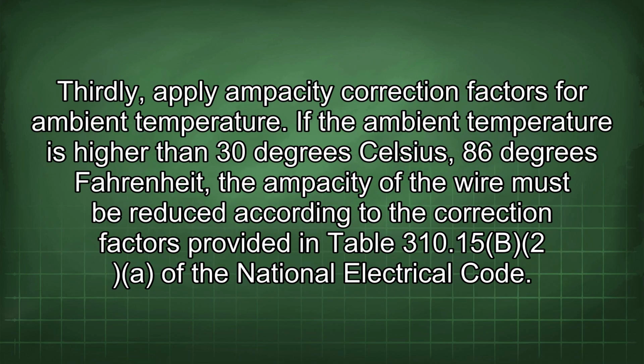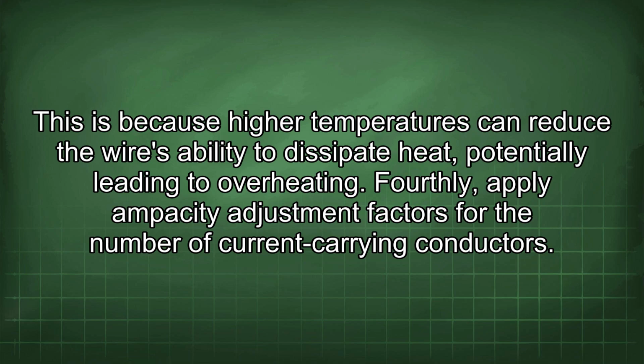Thirdly, apply ampacity correction factors for ambient temperature. If the ambient temperature is higher than 30 degrees Celsius, 86 degrees Fahrenheit, the ampacity of the wire must be reduced according to the correction factors provided in Table 310.15(B)(2)(a) of the National Electrical Code. This is because higher temperatures can reduce the wire's ability to dissipate heat, potentially leading to overheating.